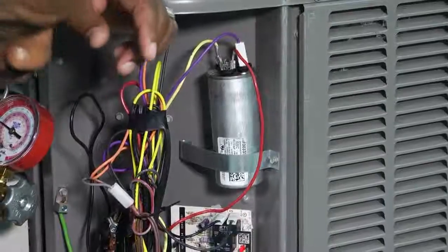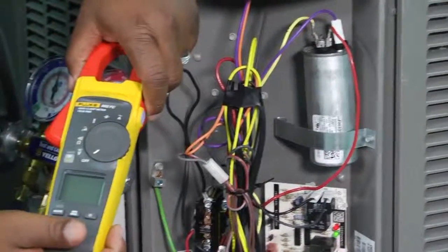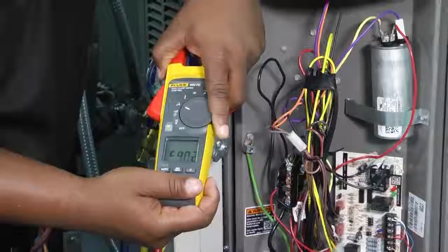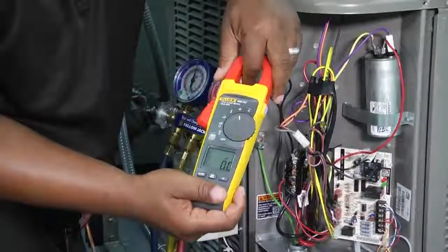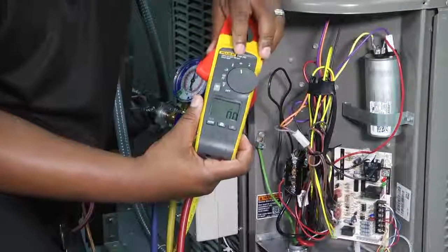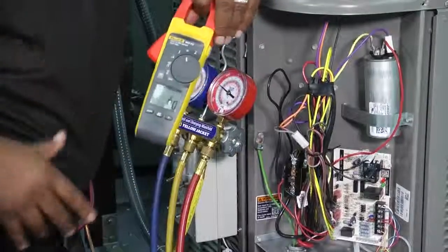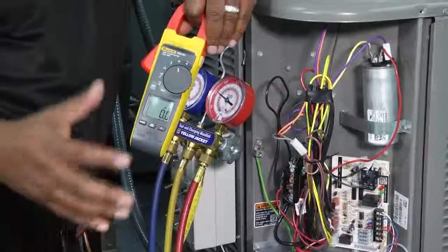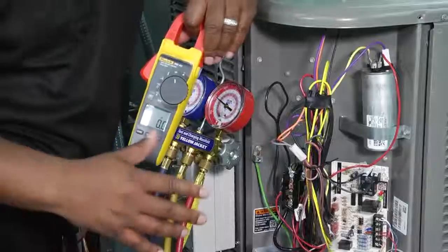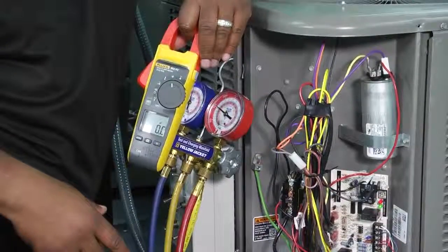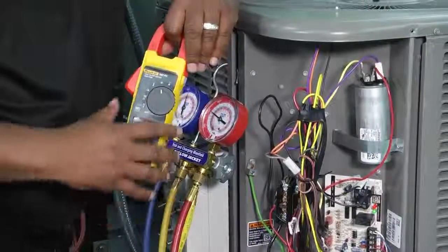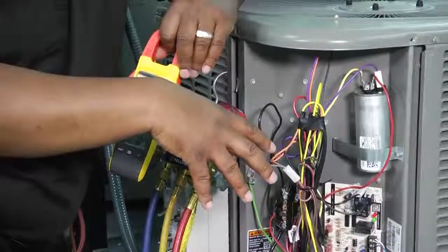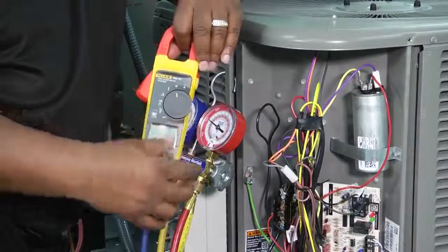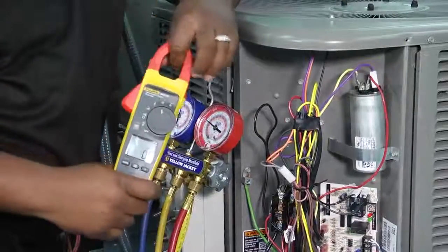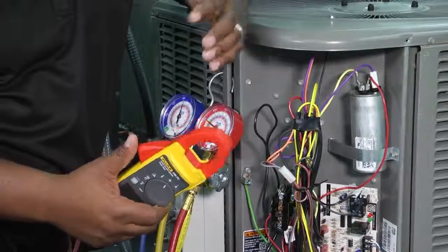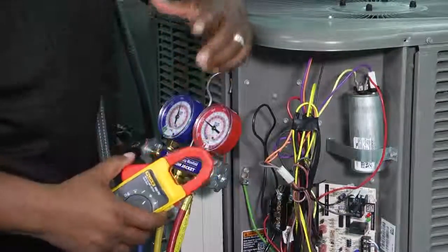So you're going to use your voltmeter here, your multimeter. Make sure you go to the proper setting for capacitance. This one happens to be the actual symbol, right? But your meter may be set up different. Some of them say MFD or whatever the setting is to check it. Now, there are two ways that people check it in the industry. One of the ways is to actually turn the system off, disconnect the capacitor, and then take your probes and check it there.